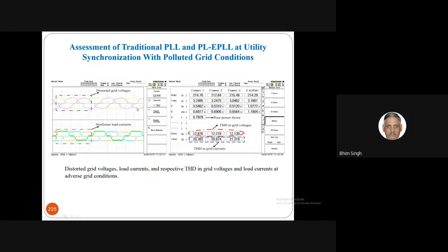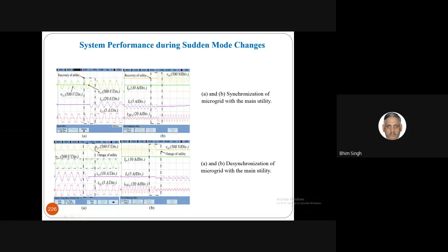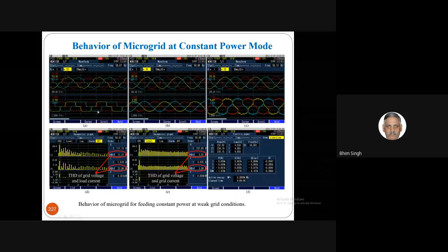Even with a normal grid and this load, the voltages are distorted. But when we switch this on, the voltages are improved. Why are the voltages improved? Because now we are not drawing non-sinusoidal current from the grid. We are making it sinusoidal, so the voltage profile is also improved under that condition. You can see when the converter system is not on, the voltages are distorted because of non-linear current. But when the inverter is switched on, the voltages are automatically improved along with the grid current being sinusoidal and balanced. And this inverter takes care of meeting the local load harmonic requirement locally.